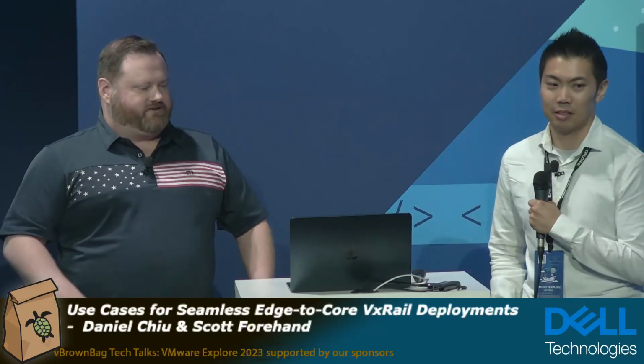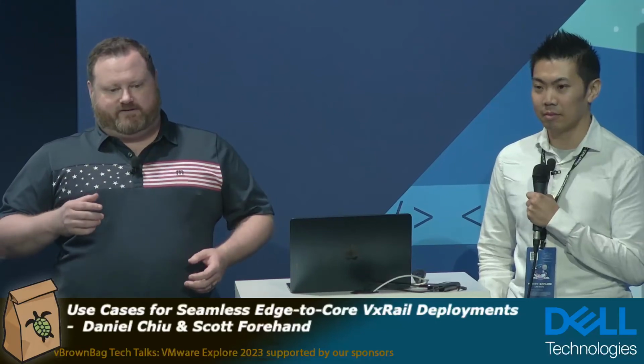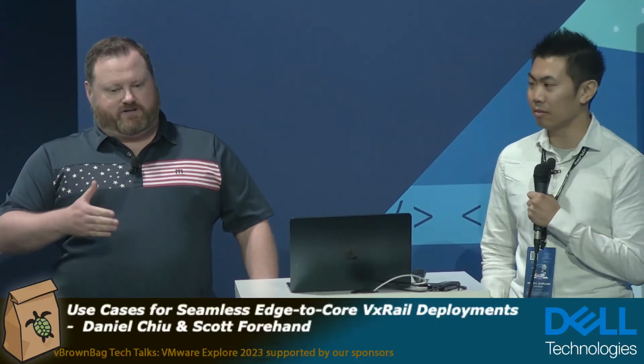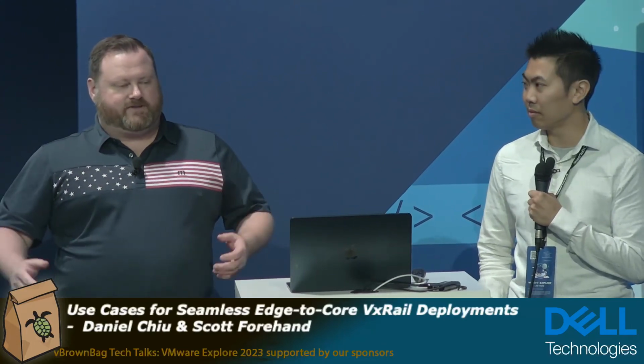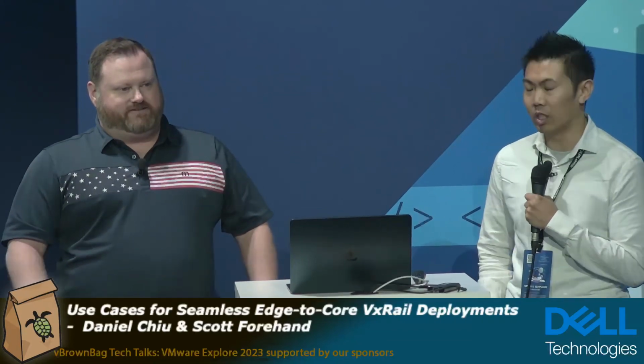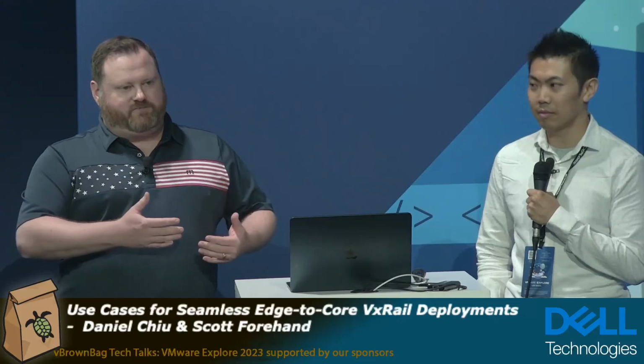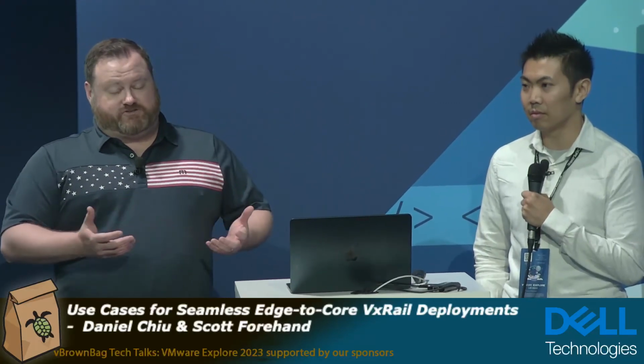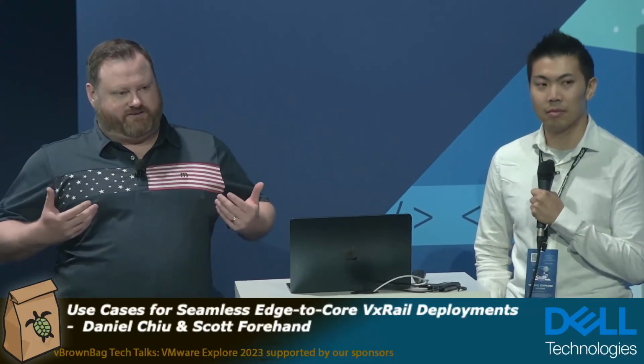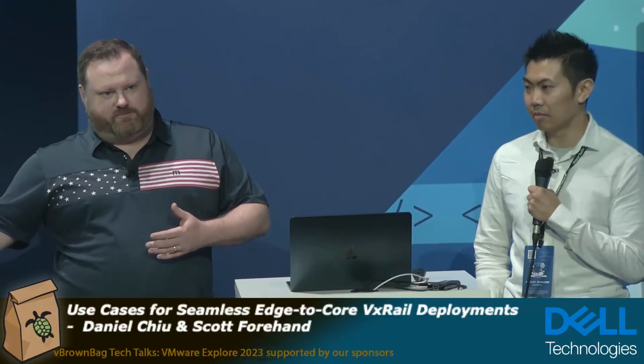Yeah, 100%. And there are also some weird things that we have to do that most of you probably don't. Two things you need to run a data center: power and cooling. If either one of those stops, it usually takes an hour to shut everything down cleanly in a typical data center. With us, we're able to do that in about 15 minutes, which has really helped open up a whole lot for us because we don't have to fix things as we bring these venues back up if they've had an issue with the power company or whatever.